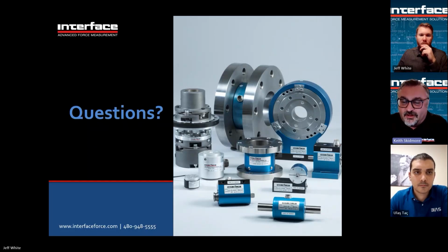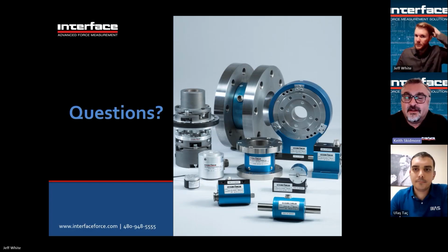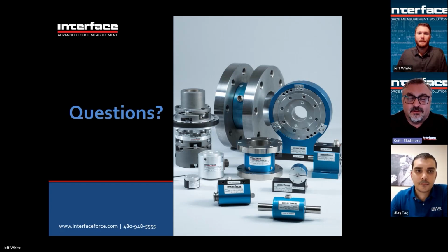We can also obviously hook up or attach to data acquisition systems that are already deployed at a customer. Sometimes they might be using something like LabVIEW, and they might want an instrument that has LabVIEW drivers or VIs. We do have certain instruments that have those. Or again, if the data acquisition system has a voltage or a milliamp or a frequency input, we can accommodate that by selecting a torque sensor that has the appropriate signal to connect straight to the data acquisition system.